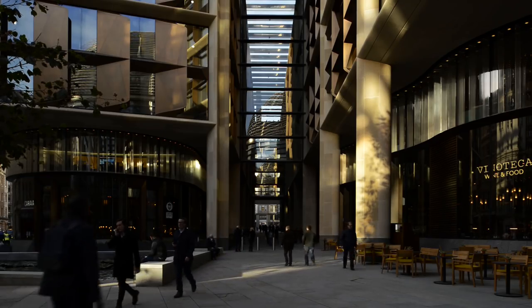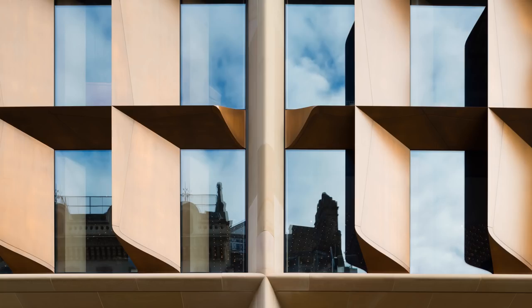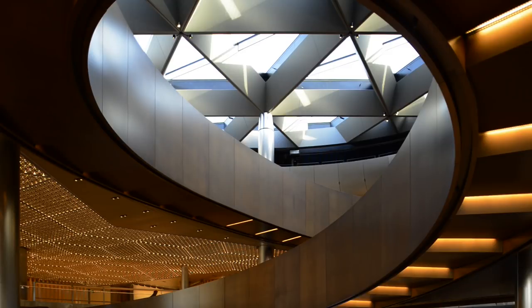The breathing building works in a very simple way. We introduce openings all around the building, largely in the bronze fins that self-shade the facades. The rear face of them is an opening vent that enables air to pass through, be drawn across the floor plates and then go up through the void around the central ramp and out through the roof light at the top.